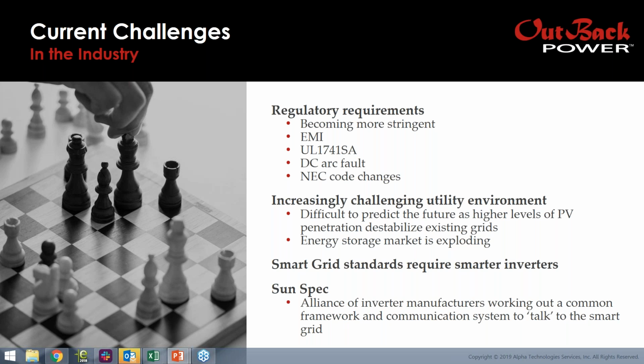Many of the older inverters simply made sine waves, or just made power. They didn't have sophisticated features other than the ability to disconnect from the grid when frequency or voltage was out of range. They couldn't supply things like reactive power factor, volt-var, or frequency-watt—smart grid standards that allow large systems to work together without direct communication.